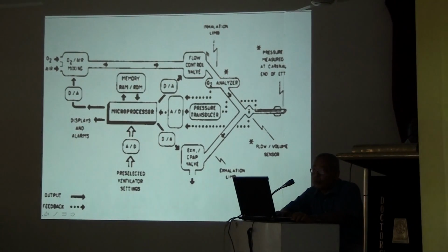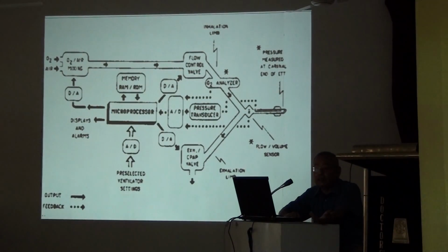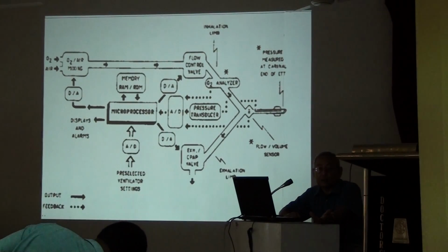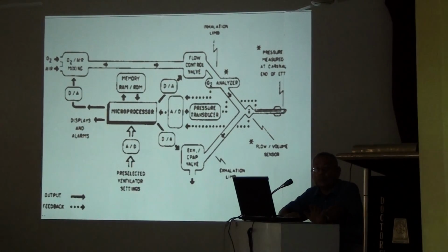So from the outside of the bonnet, you have to attach the patient circuits. This is really the patient circuits, the pipes which sit in the ventilator. It may be silicone, it may be PVC, it may be latex, anything, whatever material you use according to the price or availability, you can use any type of pipe. These are basically non-kinkable patient breathing circuits. Once you open this control valve, the air will start passing out through this pipe with a hissing noise.